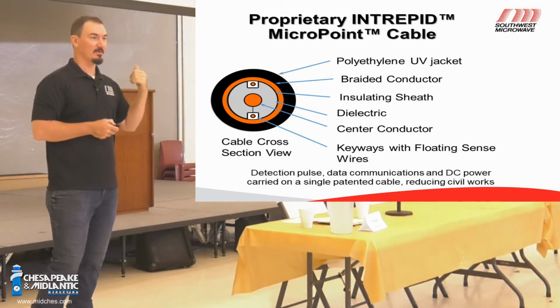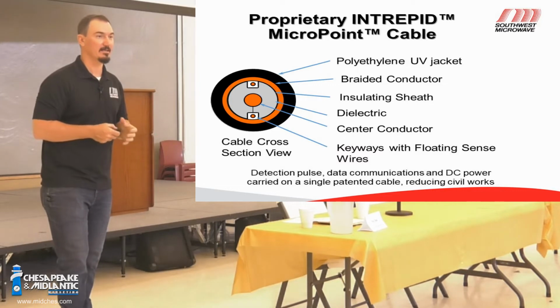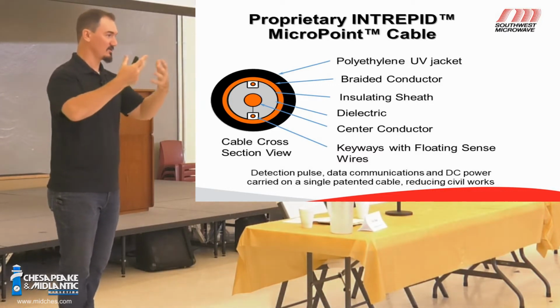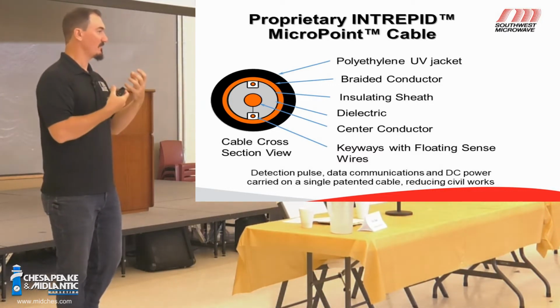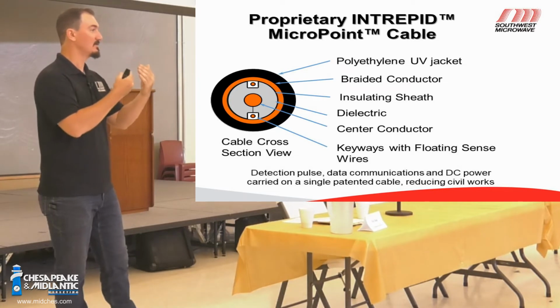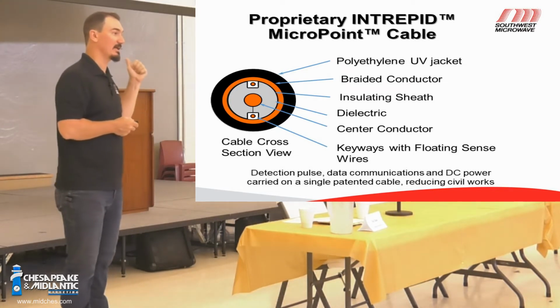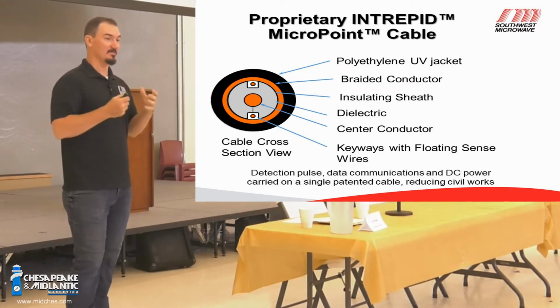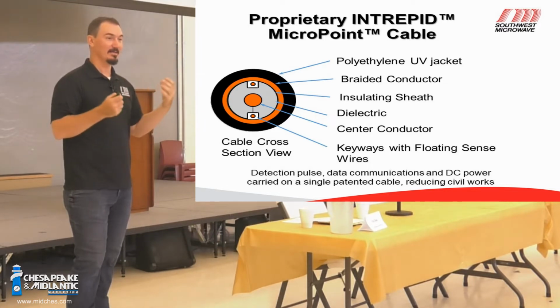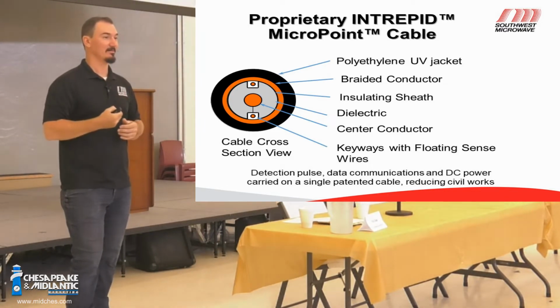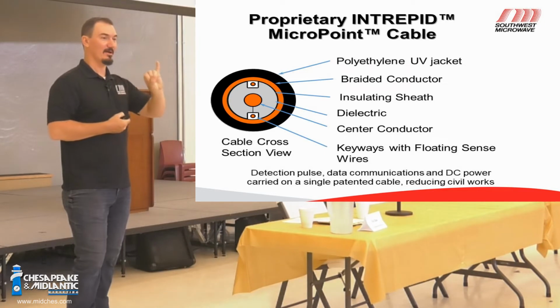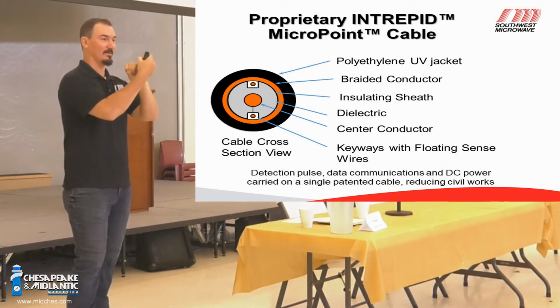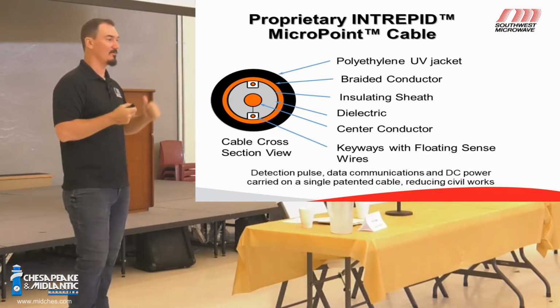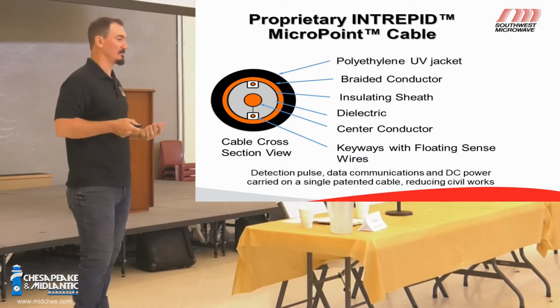right? This cable is a living, breathing thing. When it gets hot outside, it expands, draws air and moisture in. When it gets cold, it contracts and it pushes that out. Well, what can happen if you don't put the dielectric grease on here is it expands and draws humidity in, it contracts and it pushes it further down. So if you have that braid with a tinfoil shielding, those are two metals touching each other inside the sensor cable. You add moisture to that, and now you're going to get corrosion.